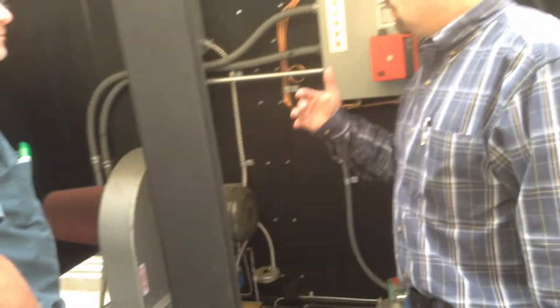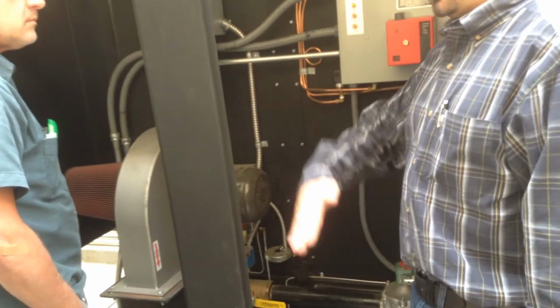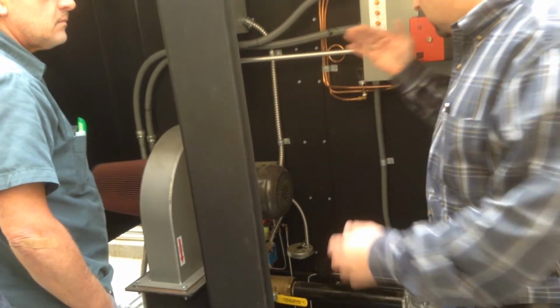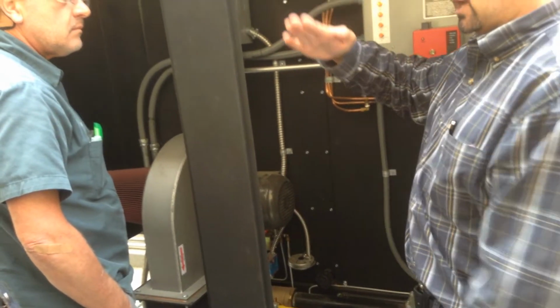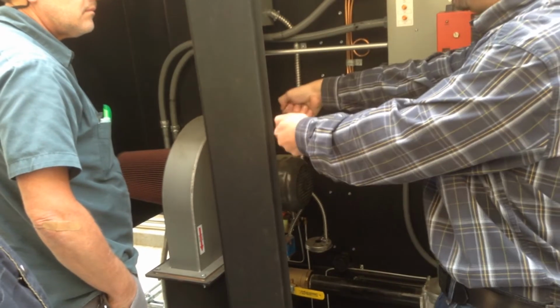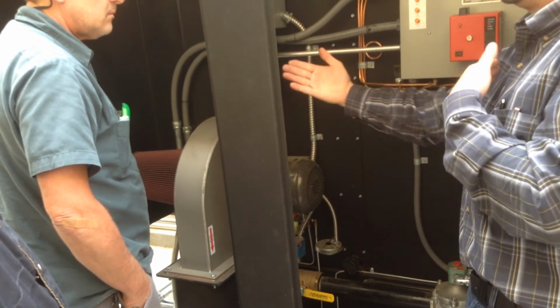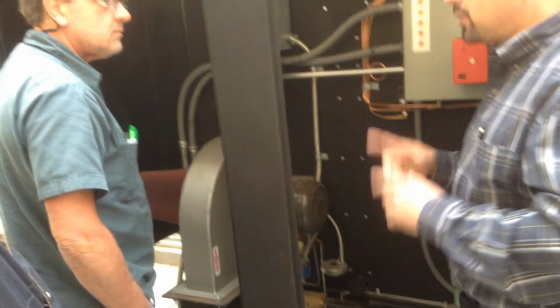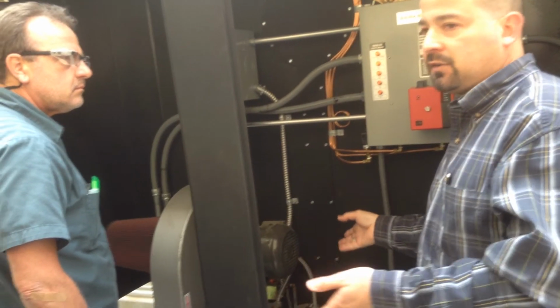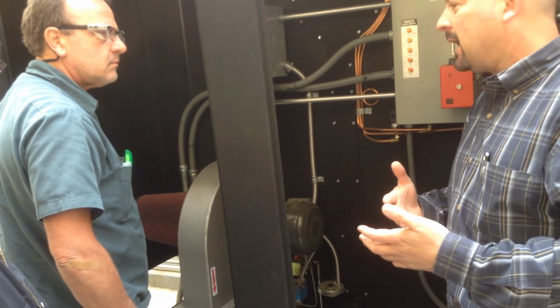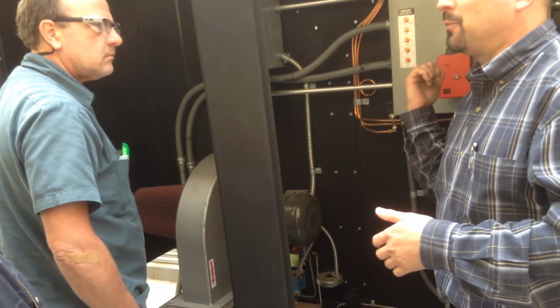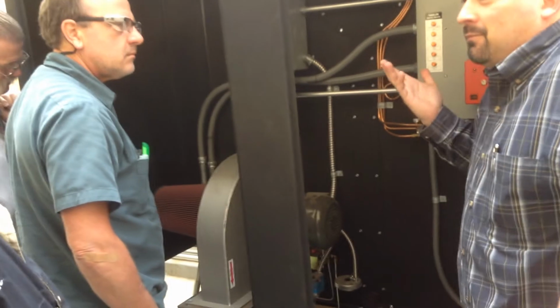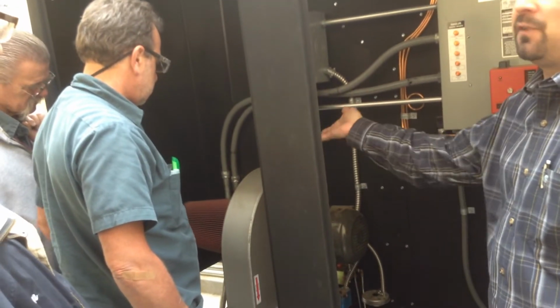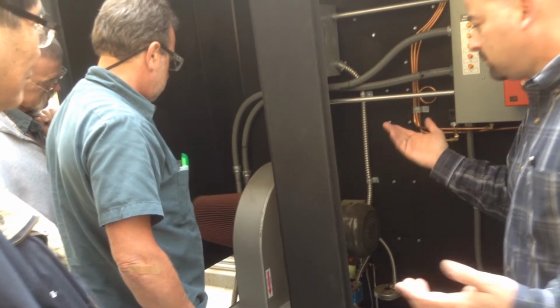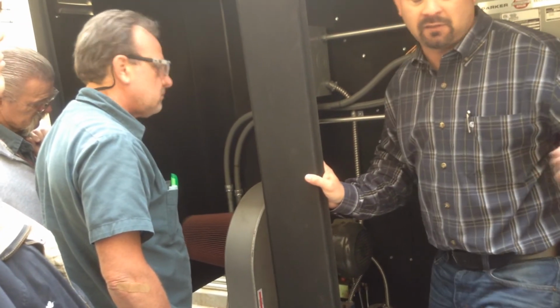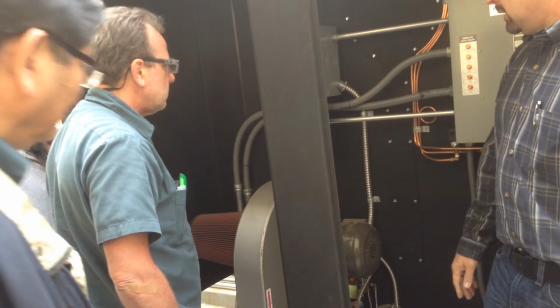So the gas follows the air. So you've got more pressure on your air, you get more gas, and vice versa. If you've got not a whole lot of pressure, like let's say you put a bag over that, you're not going to have any gas. So it works in direct ratio. So good and bad. Good because you don't soot up the firebox, you don't damage the burner, you don't do any of that. Bad because you might be running a 90 horsepower boiler at 40 horsepower because it's derated automatically when it's dirty. So keep the filter clean. Probably want to order a spare, have one available, especially if they use leaf blowers around here. That's a big thing that gets them dirty.